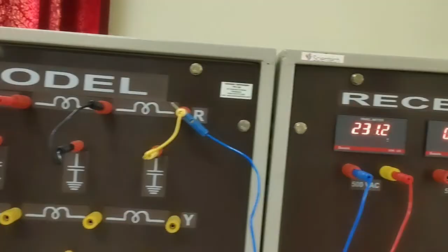Previously we calculated with the rated voltage and the receiving end open circuited. Now we give the supply at the sending end with the receiving end shorted through the ammeter. The rated current is 5 amps.